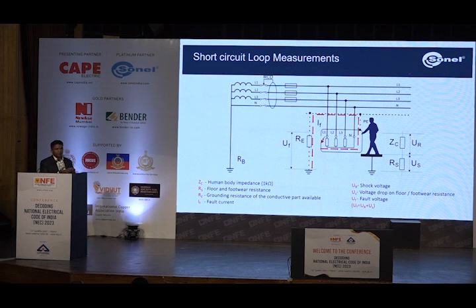You connect an equipment, calculate the prospective short circuit current, and once you see your impedance value, you can do it in any socket wherever you're connecting. That impedance value is clearly mentioned in your standard document for TN system, TNS system, and for each type of circuit breaker, what is the tripping time.